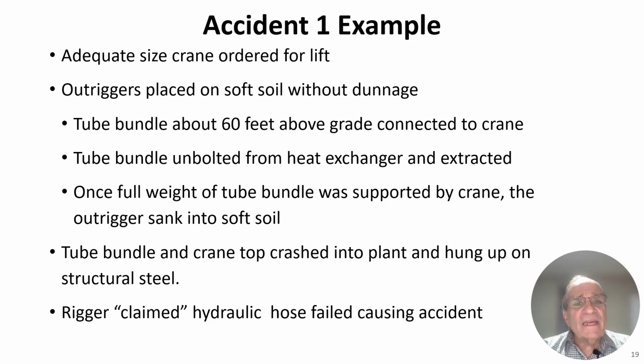I'll give you two examples that I have firsthand knowledge of. Adequate size crane was ordered for a lift. Outriggers were placed on soft soil. The tube bundle was about 60 feet above the grade, connected to the crane. This is a tube bundle for a heat exchanger. The tube bundle was unbolted and removed from the heat exchanger. Once the full weight of the tube bundle was supported by the crane, the outrigger sank into the soft soil.